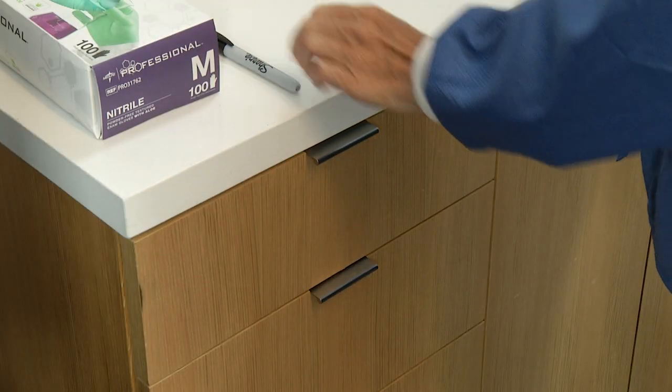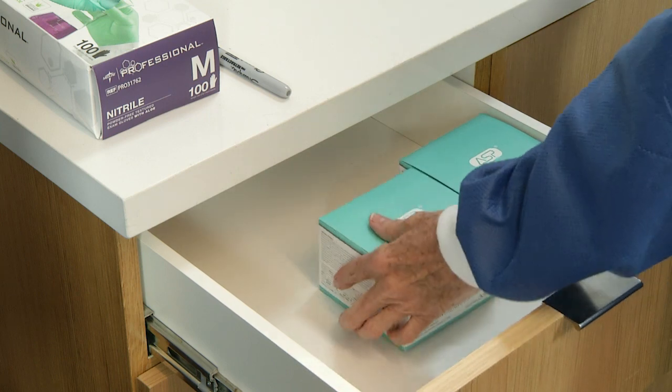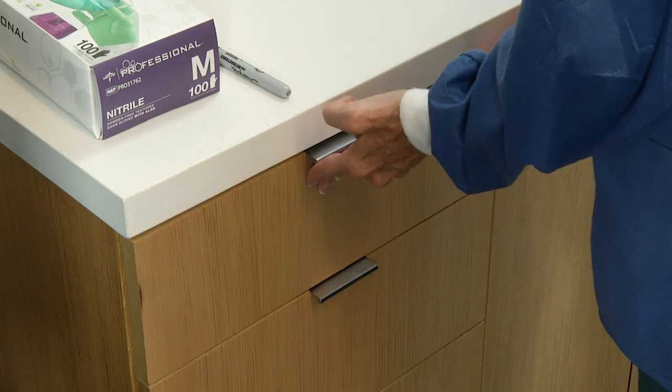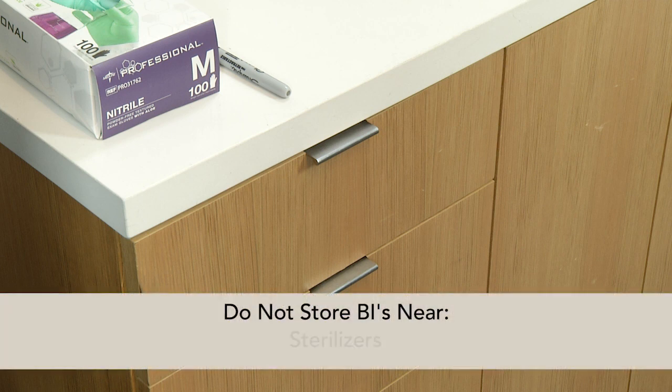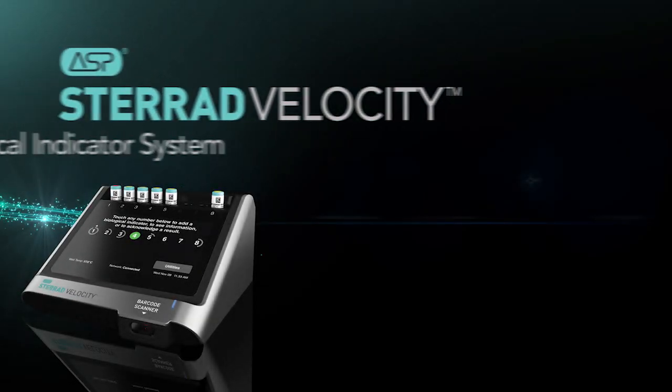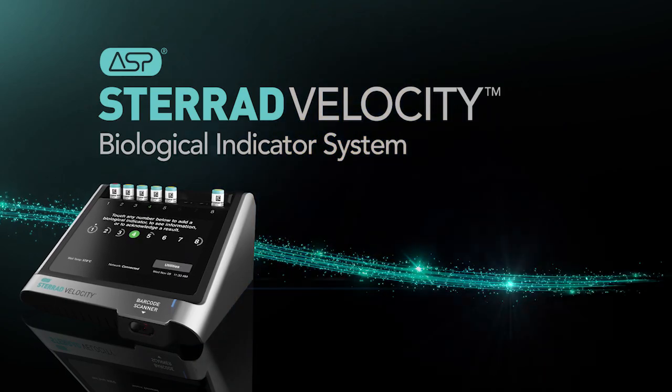Once opened, the BI should be stored between 41 degrees to 77 degrees Fahrenheit at or below 50% RH. Do not store near any sterilizer, sources of ethylene oxide, hydrogen peroxide, acids, alkalis, or volatile antimicrobials such as glutaraldehyde or formaldehyde, STERRAD cassettes, or any other oxidizers.